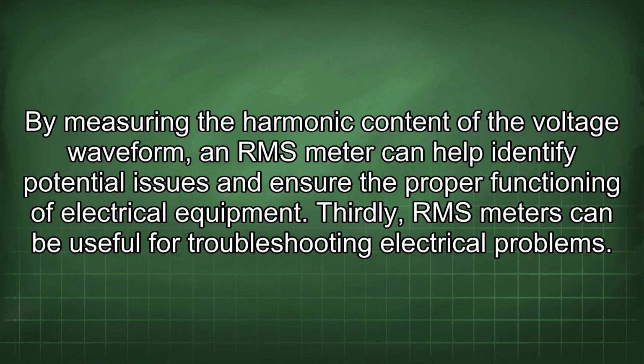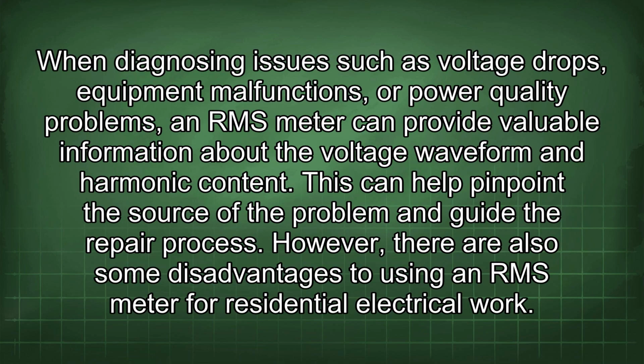Thirdly, RMS meters can be useful for troubleshooting electrical problems. When diagnosing issues such as voltage drops, equipment malfunctions, or power quality problems, an RMS meter can provide valuable information about the voltage waveform and harmonic content. This can help pinpoint the source of the problem and guide the repair process. However, there are also some disadvantages to using an RMS meter for residential electrical work.